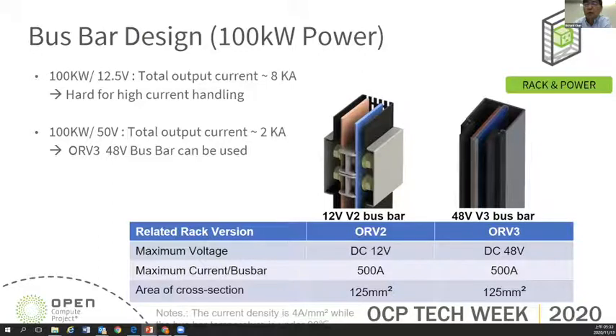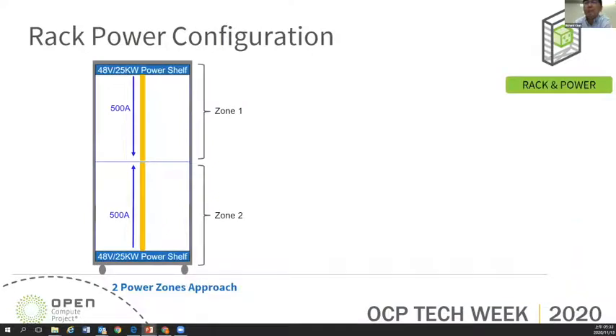So I think the V3 48 volt bus bar can handle it. So let's make an example of that here. For example, we have a 500 amp bus bar and the voltage is 48 volt. So that means if we put up 2 power zones, each power zone can handle around 25 kilowatt. So totally it is 50 kilowatt.